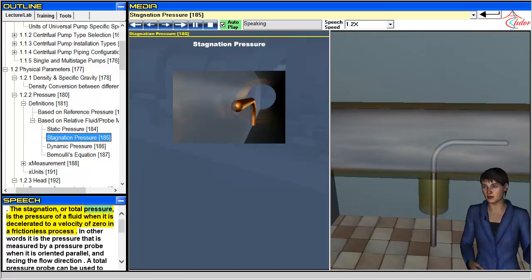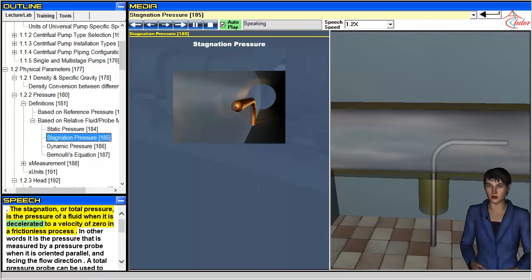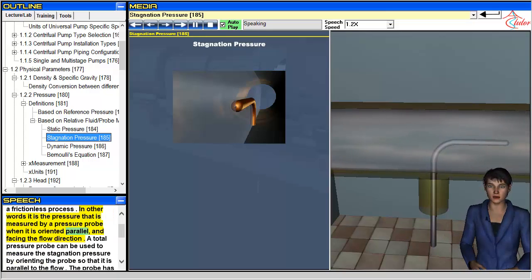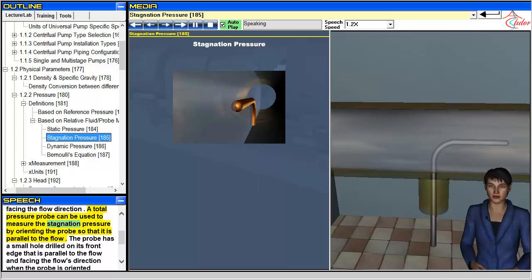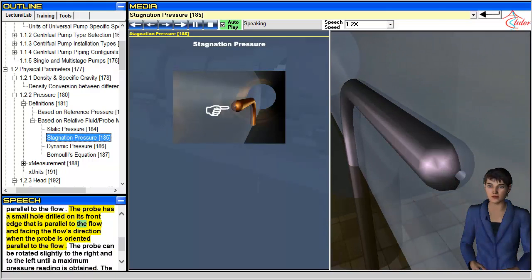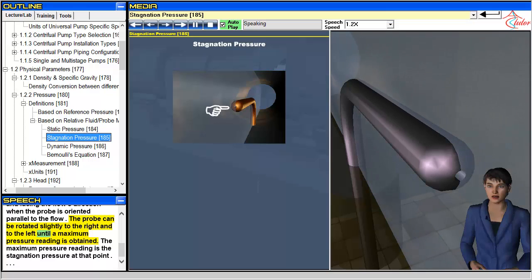The stagnation, or total, pressure is the pressure of a fluid when it is decelerated to a velocity of zero in a frictionless process. It is measured by a pressure probe oriented parallel to and facing the flow direction. A total pressure probe has a small hole drilled on its front edge facing the flow. The probe is rotated slightly right and left until a maximum pressure reading is obtained, which is the stagnation pressure at that point.